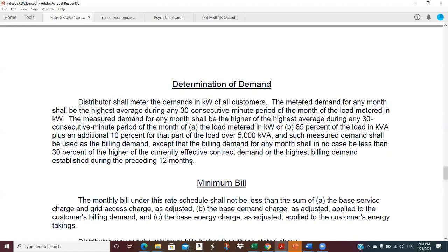We sat there and we said, hey, either you guys are really consistent or this is on your contract demand. And the utility guy was there and he said, yeah, it was 1,500, whatever the number was. He said, they're paying on that. I said, well, you need to renegotiate this. If you're not going to go back up in demand, then you need to renegotiate this. Because you can call them in and renegotiate. Of course, they're liable to decrease one thing and increase something else, but anyway, you can certainly try. Okay.